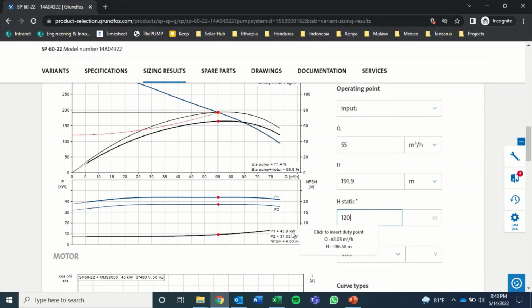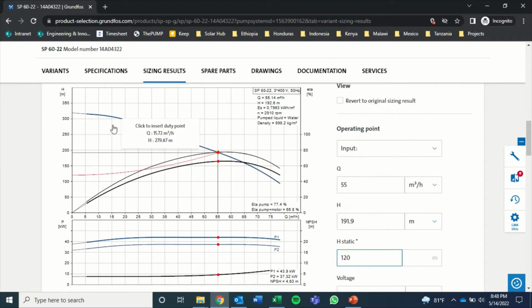You can also see your P1 and P2 information for 43.9 kilowatts for P1, your pump and motor efficiencies, which are represented by these two curves, where the top curve is the pump efficiency and the bottom curve is the pump plus motor efficiency, and this blue curve is your pump curve. So where your head and flow intersect the blue curve will be your operational point.